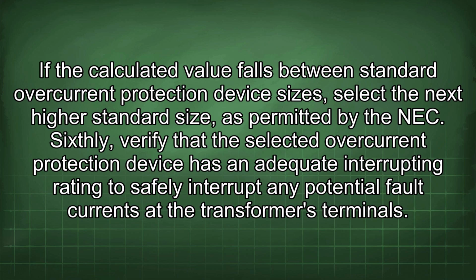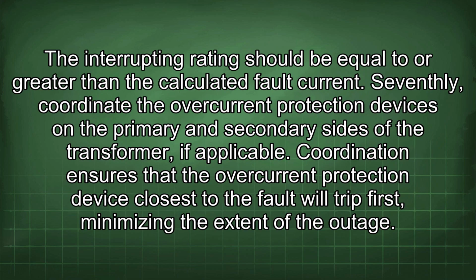Sixthly, verify that the selected overcurrent protection device has an adequate interrupting rating to safely interrupt any potential fault currents at the transformer's terminals. The interrupting rating should be equal to or greater than the calculated fault current. Seventhly, coordinate the overcurrent protection devices on the primary and secondary sides of the transformer, if applicable. Coordination ensures that the overcurrent protection device closest to the fault will trip first, minimizing the extent of the outage.